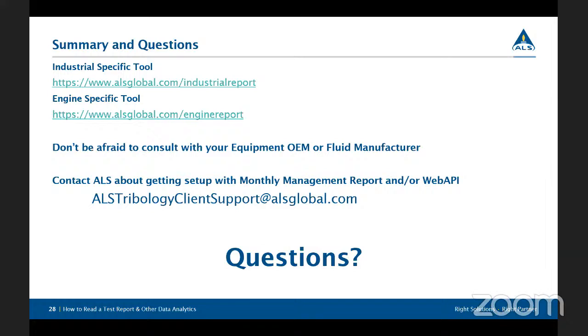All right. Mark, in situations where the oil is in a machine for a long time but does not get used for very many hours, what is the indicator that would tell you that an oil change needs to occur more frequently? All right, let me think through this real quick. If it's in for a long time and it doesn't get used, you'd want to think about condensation.